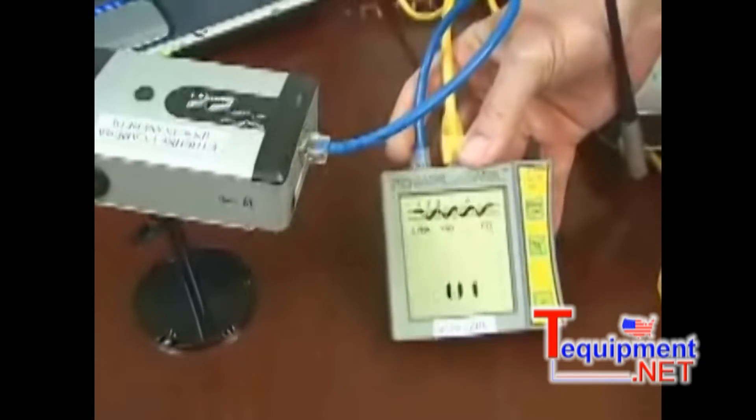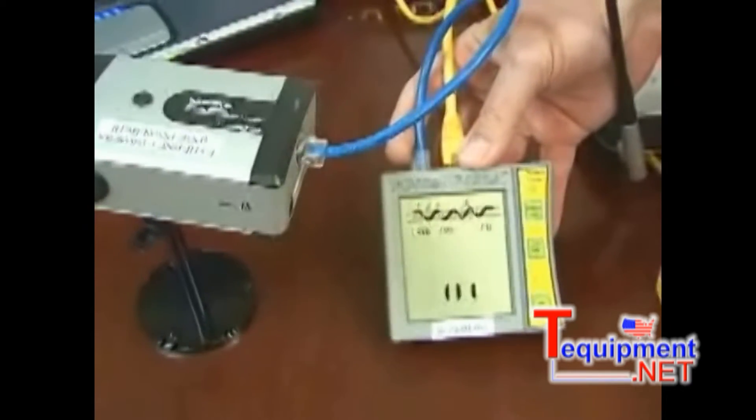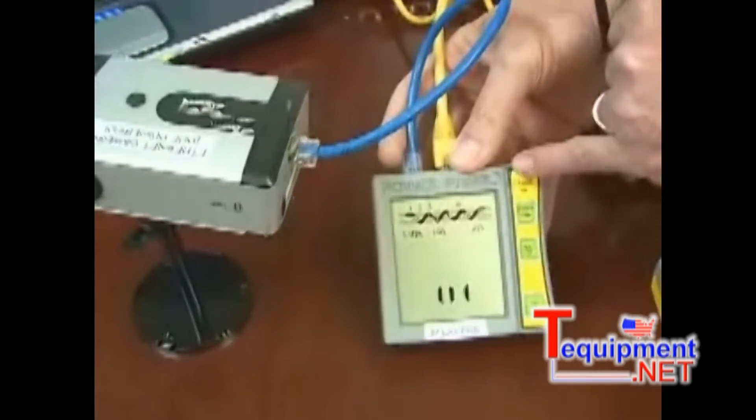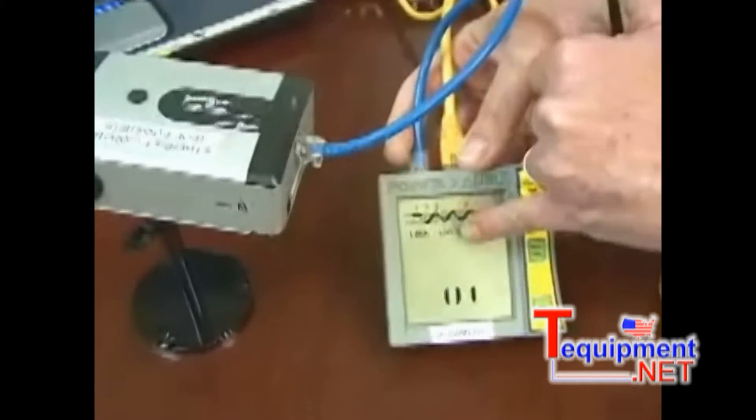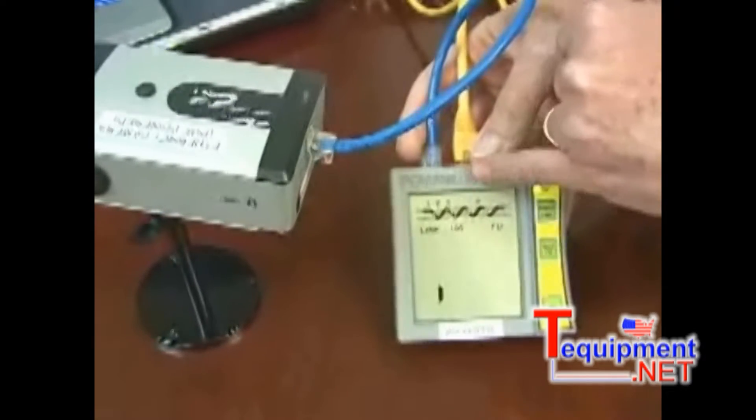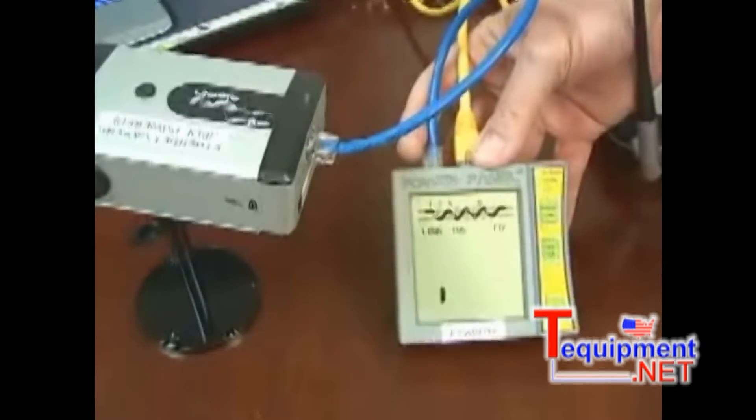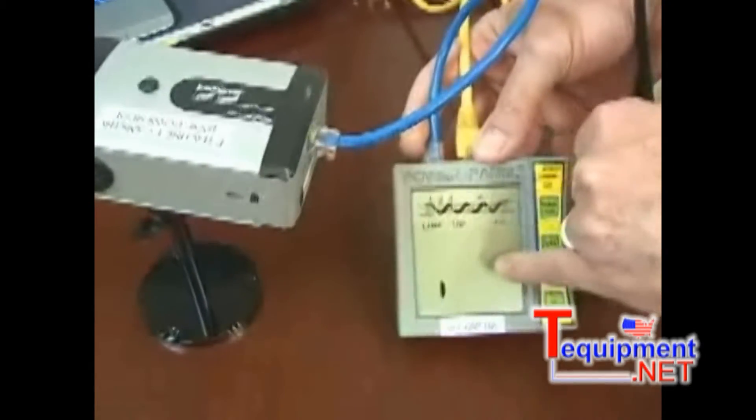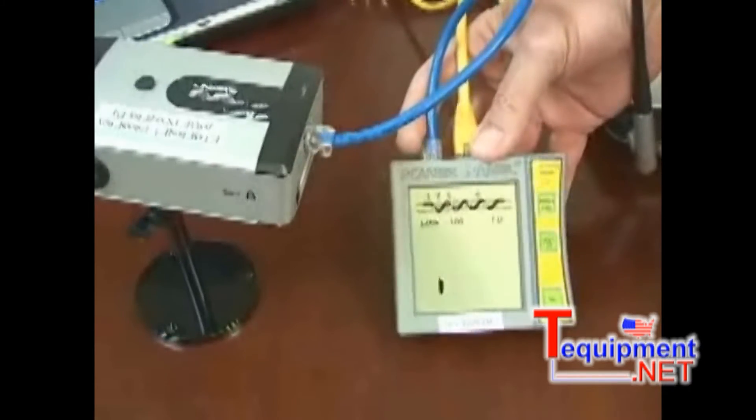If I wish to learn more, I go to the correct screen. Here I am on the network screen and it says that it sees a device that is 100 Mbit a second full duplex on 1, 2 and 3, 6. I also see that data is flowing by looking at my dancing data display.